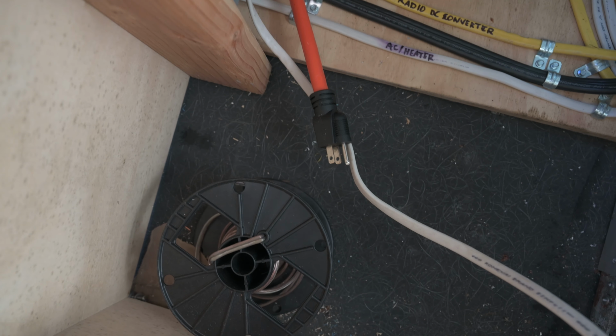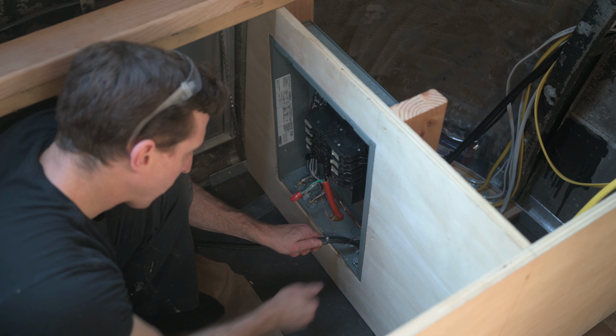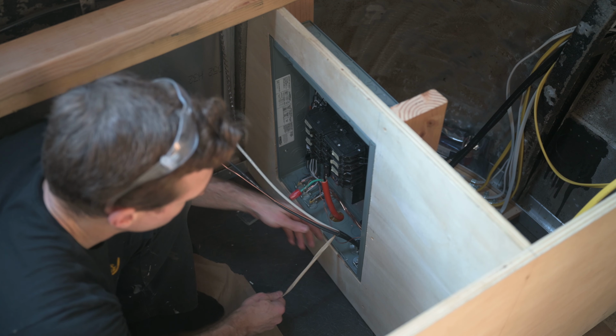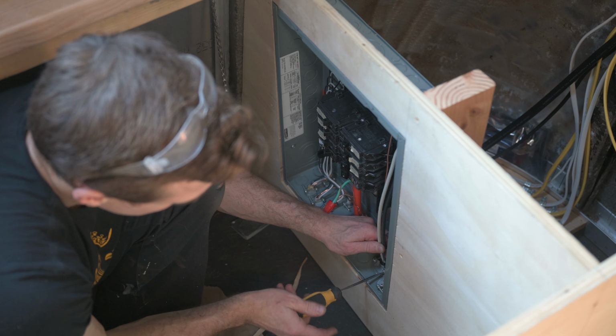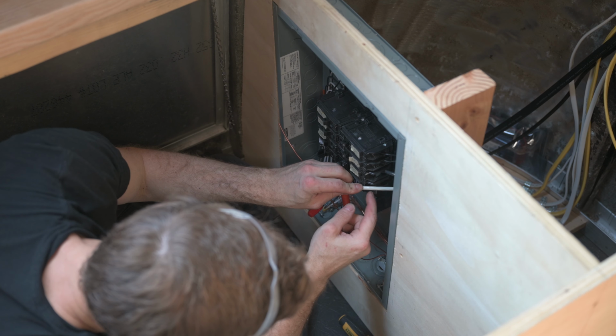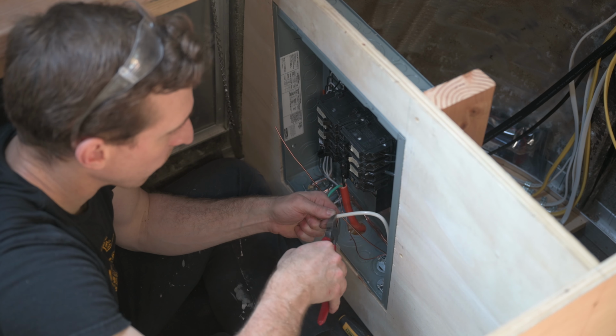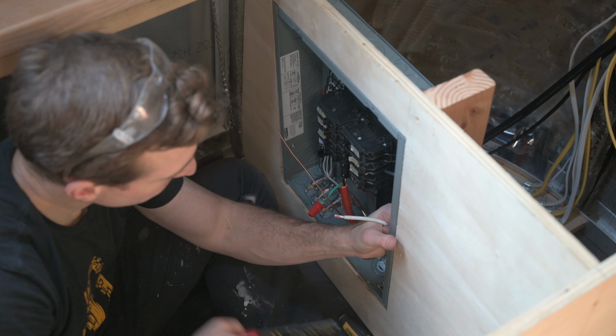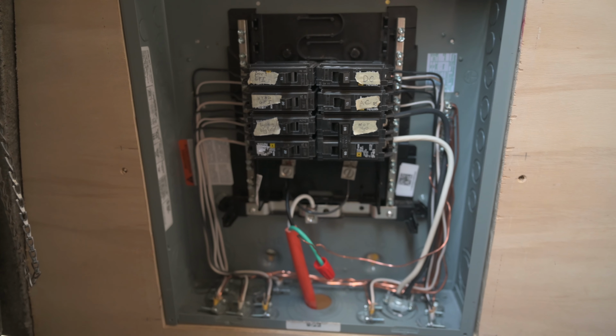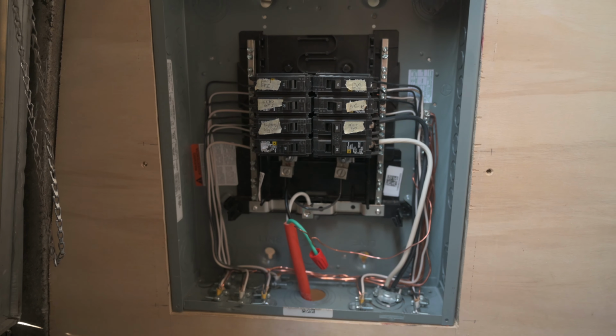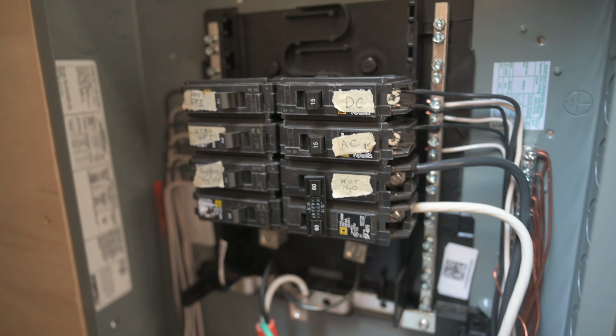As always, make sure your panel is unplugged anytime you're working on it. With all the cables run, it's time to finish up the wiring in the breaker panel. Again, make sure your cables are labeled. We put in this piece of wood behind it to secure the cables in an orderly way and labeled them there as well. From there, figure out where each cable is going to be held in a clamp and strip off the insulation down to that point. Then tighten up the clamp. Then figure out how long each wire needs to be to reach its breaker or terminal. Cut its length, strip it back, and screw it in. I tried to keep it neat by running wires in groups and making 90-degree bends in the wires. Pretty satisfying.